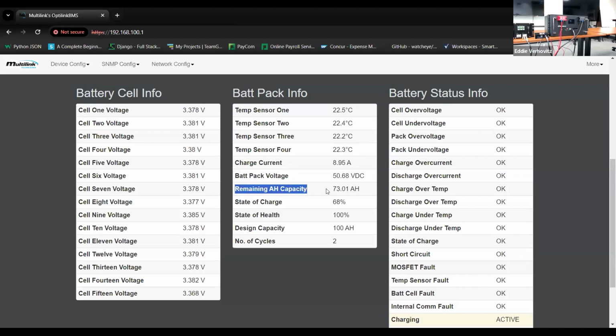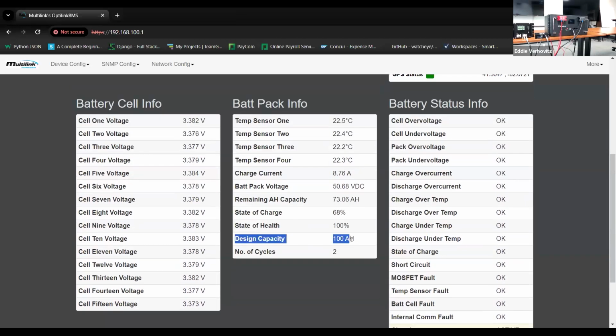During the recharge state, we can see our amp hour capacity actually increase during recharge. Our state of charge is currently set to 68, and state of health is 100%. The design capacity, in case you're not familiar with the model number and its scheme, is shown here, along with a brief history of the number of full cycles that has occurred with the power supply and batteries.